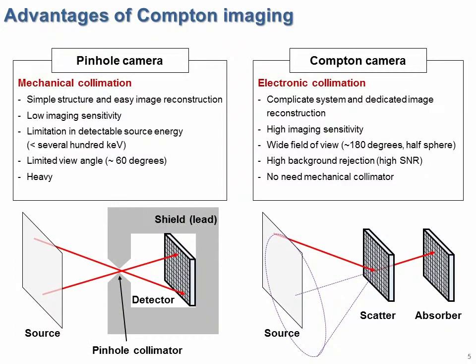Pinhole cameras are generally used for the same purpose. However, pinhole cameras use a mechanical collimator and therefore cannot be used to image high-energy gamma rays. On the other hand, Compton imaging filters effective events by electronic collimation, so it provides high accuracy and high efficiency for high-energy gamma rays.